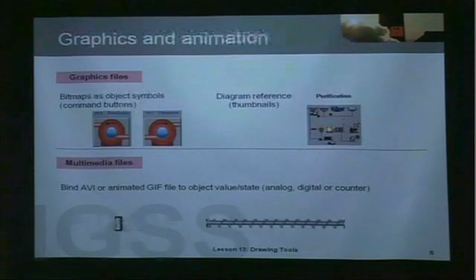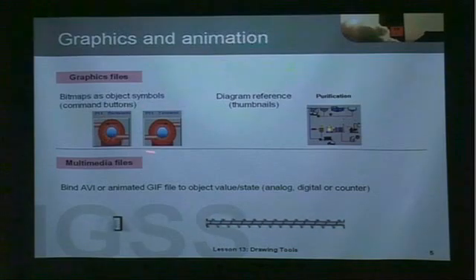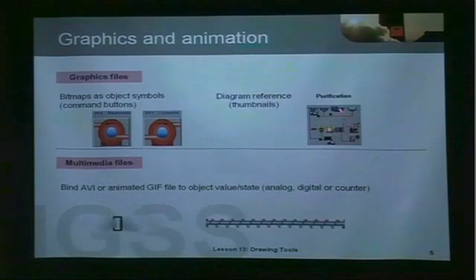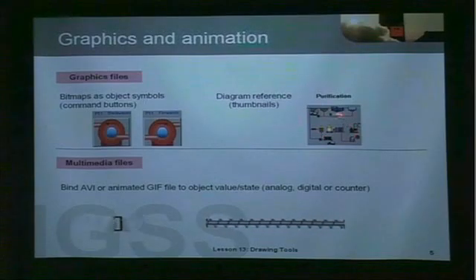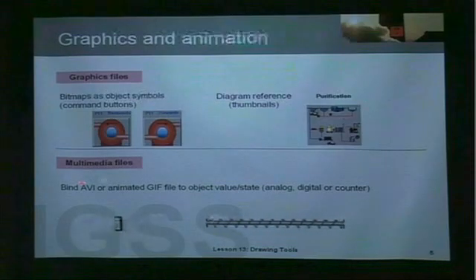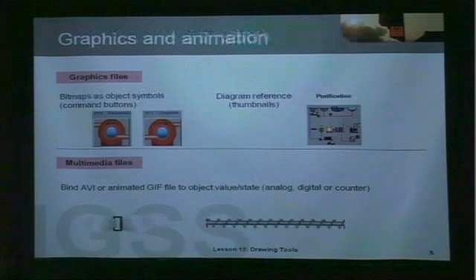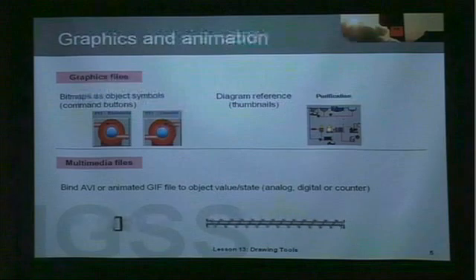Then we have the fun section: graphics, files, and animation. Graphics can be used for different states of a digital object — we see two different graphics here for two different states or commands for a digital object. You can use graphics for diagram references or thumbnails, so you can have a mini mimic diagram on your overview diagram linking to the actual sub-diagram. You can also bind AVI files or animated GIF files to the value or state of an IGSS object, so when the motor runs, the animation will also run.